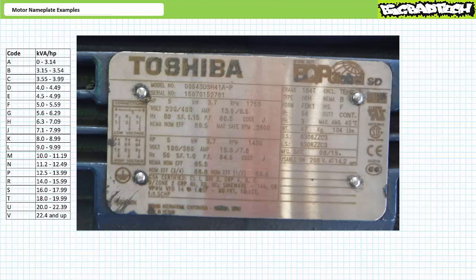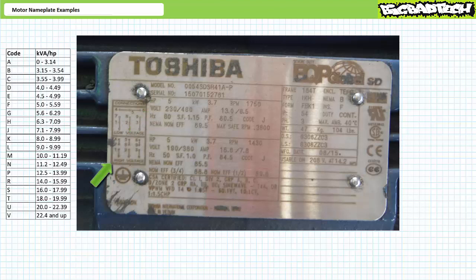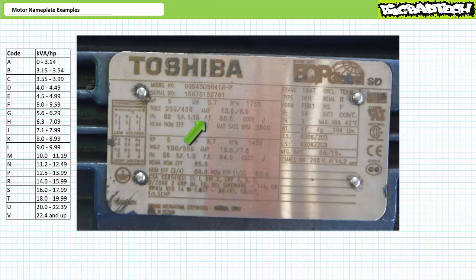Restricting our analysis to the 60 Hz entries, this is a three-phase motor intended to operate at 60 Hz. It's a dual voltage motor that can operate at 230 volts in the low voltage configuration and 460 volts in the high voltage configuration. Connection diagrams on the nameplate illustrate exactly how to set the motor up for high or low voltage operation. Swapping any two applied phase sequences would reverse the motor's direction. In the low voltage configuration it draws 13 amps at rated condition; in the high voltage configuration it draws 6.5 amps. At rated condition it has a power factor of 0.805 and operates at 89.5% efficiency. The inrush code appears to be J.